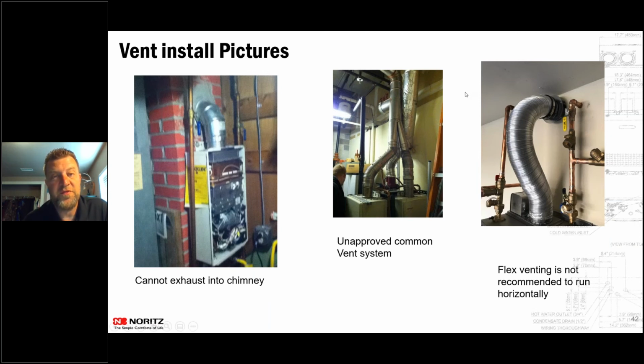But with every 90 that you add to that system, you could be 65 feet with 2-inch, but that's just a straight length. You add a 90, you need to take 6 feet off of it. We actually have apps that you log into and put your install in there. So if you're going 35 feet with 3 90s, it will tell you that yes, you can do that, and tell you what dip switches inside the unit to set to let the unit know what type of install it's in. Okay, cool. Thank you.